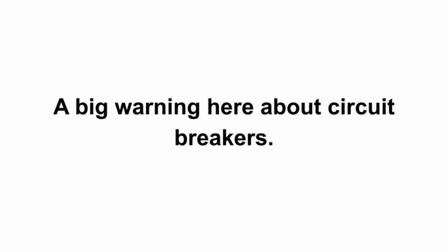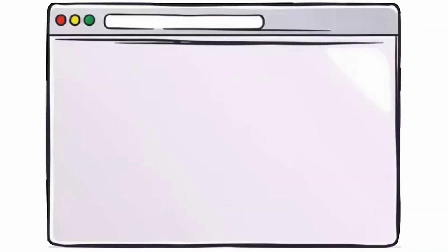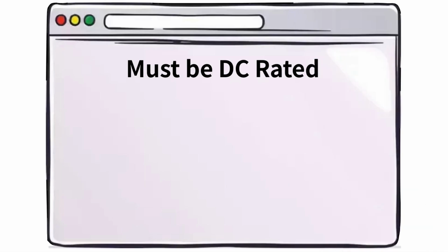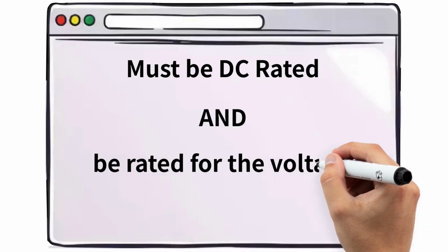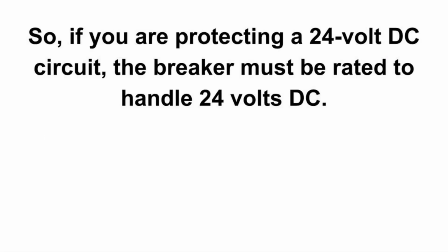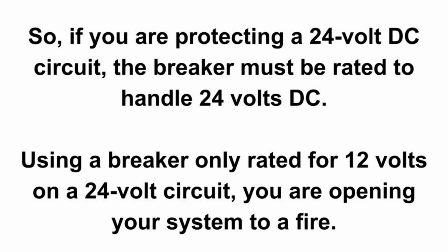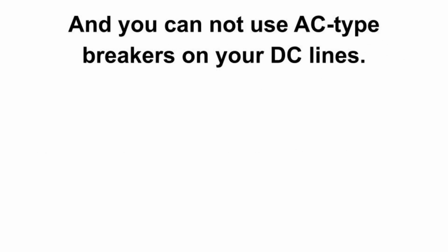A big warning here about circuit breakers. When using circuit breakers on your solar system, they must be DC rated and be rated for the voltage you are protecting. So, if you are protecting a 24-volt DC circuit, the breaker must be rated to handle 24 volts DC. Using a breaker only rated for 12 volts on a 24-volt circuit, you are opening your system to a fire, and you cannot use AC-type breakers on your DC lines.